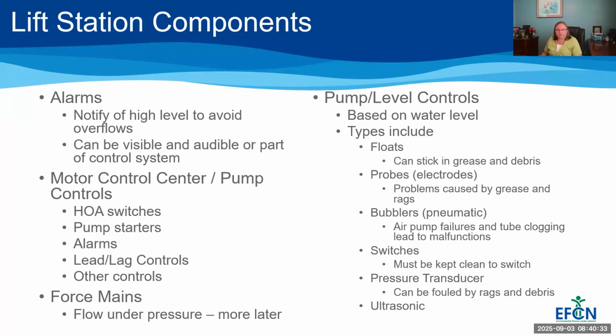And then pressure transducers, these are submerged. The pressure is created by the head, the pressure from the water level, and it's pushing on this flexible membrane, and that's converted to an electrical signal. And then finally, ultrasonic transducers. There's an ultrasonic pulse that hits the water from the top, from the surface, and bounces back. However long it takes that pulse to go down and back is what's used to determine the depth of the water. So, different types of level controls that you should be familiar with.